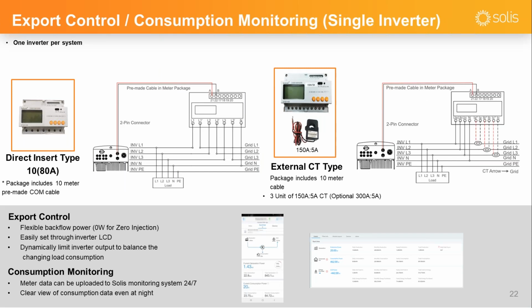The direct insert type's max current is 80 amp, and for the External CT Type we have by default 3 units of CT of 150 amp to 5 amp, and optionally we can also offer 300 amp to 5 amp CT for this meter, but you need to change the CT ratio settings inside the meter. So it depends on your system configuration, and we can provide different CT options.